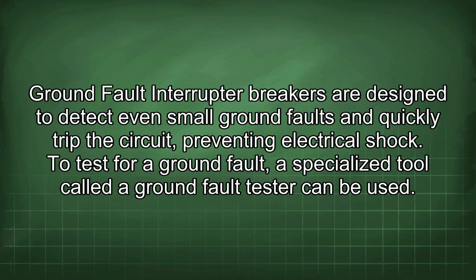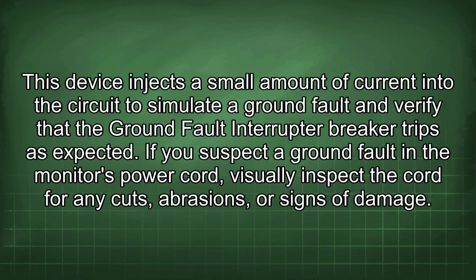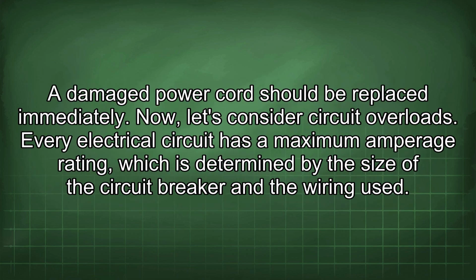To test for a ground fault, a specialized tool called a ground fault tester can be used. This device injects a small amount of current into the circuit to simulate a ground fault and verify that the ground fault interrupter breaker trips as expected. If you suspect a ground fault in a monitor's power cord, visually inspect the cord for any cuts, abrasions, or signs of damage. A damaged power cord should be replaced immediately.